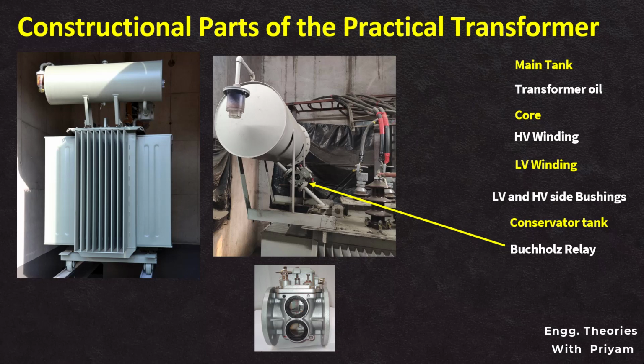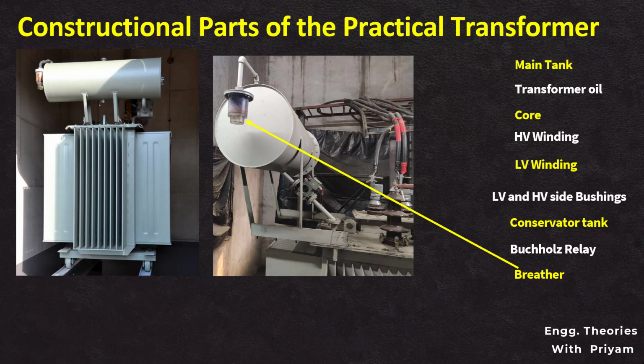Next component that we want to talk about is the breather. A breather is an accessory of liquid immersed transformers attached to the conservator tank. They serve as breathing point of the transformer. The breather is typically positioned on the transformer tank, serving as a vital component in managing the transformer's oil condition. Located at top of conservator, the breather contains silica gel which absorbs the moisture from the air entering the transformer. As the temperature variation causes the oil to expand and contract, the breather allows the exchange of air, preventing the moisture ingress that could otherwise compromise the insulation properties of the transformer oil.